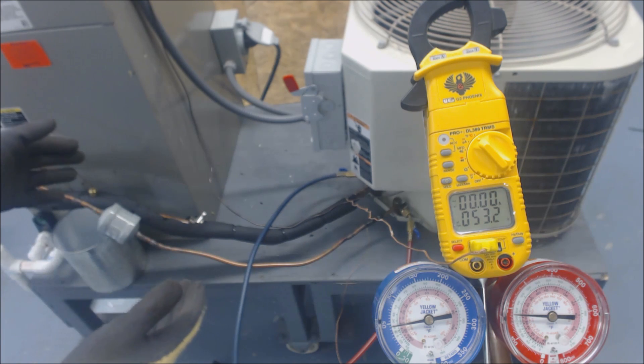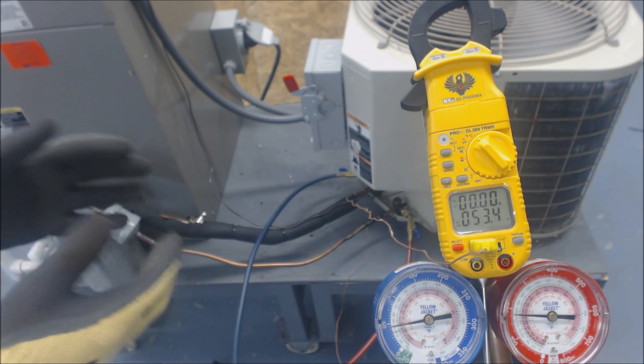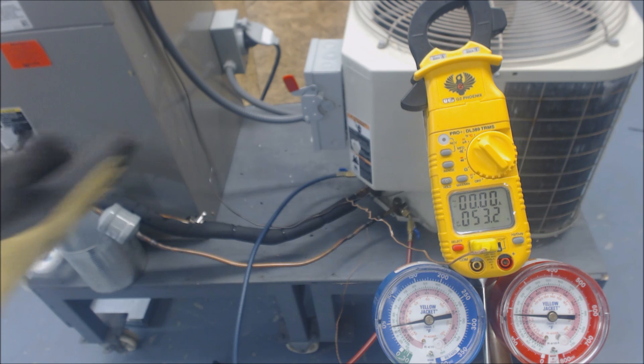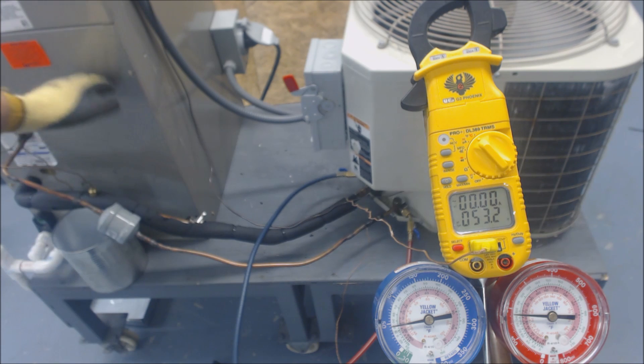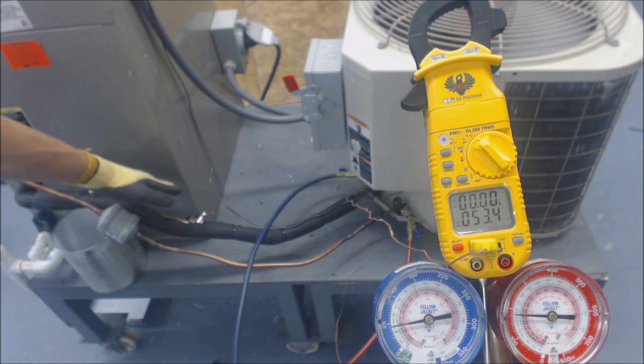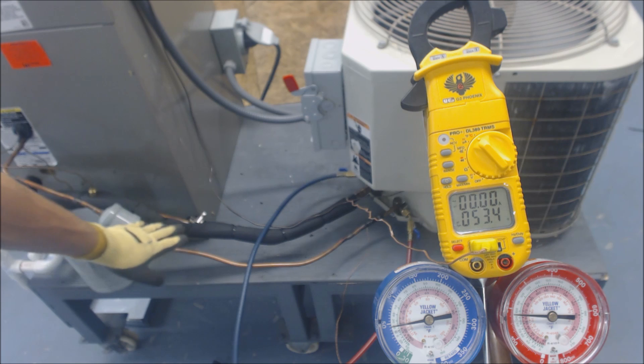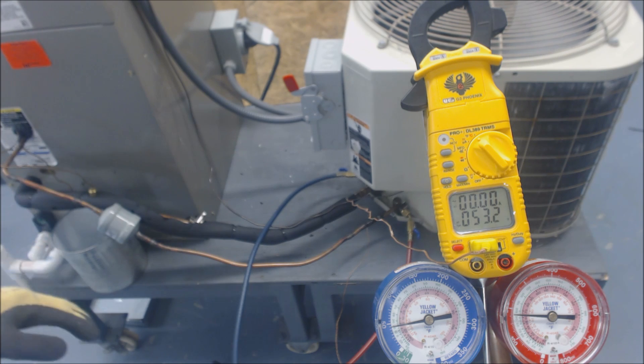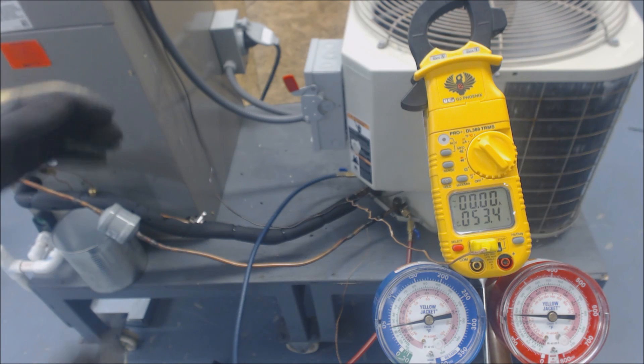In the case of ice water, what's actually happening is the TXV thinks that this line is very cold, which means the house must be extremely cold. In that case, the TXV is thinking that since it's so cold in the house or building, we do not need to put that much refrigerant through into the evaporator coil. Let's put just a little tiny amount in.